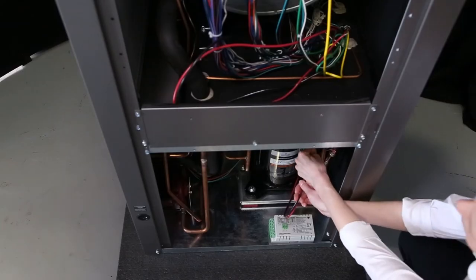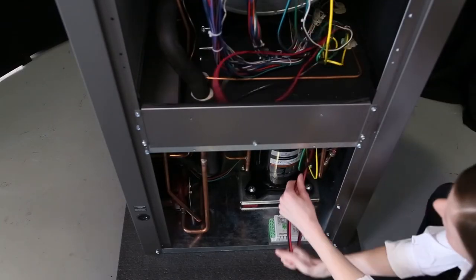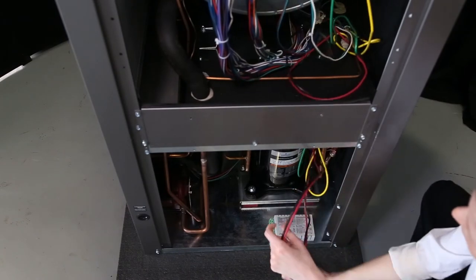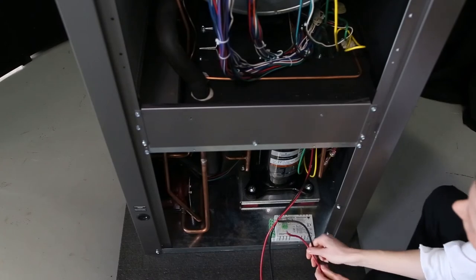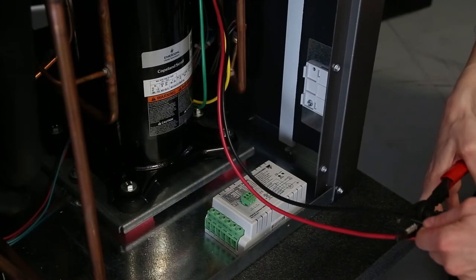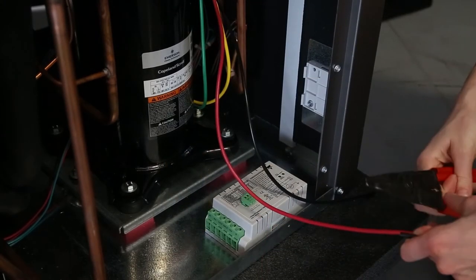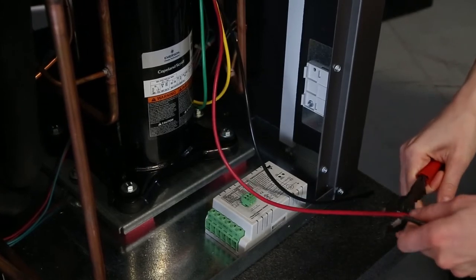Take the black and red 10 gauge wires, the ones that were disconnected from the contactor, and route them through the wiring access hole at the bottom of the blower compartment into the compressor section. Cut off any excess wire length, remembering to leave enough slack in order to mount it to the metal bracket.